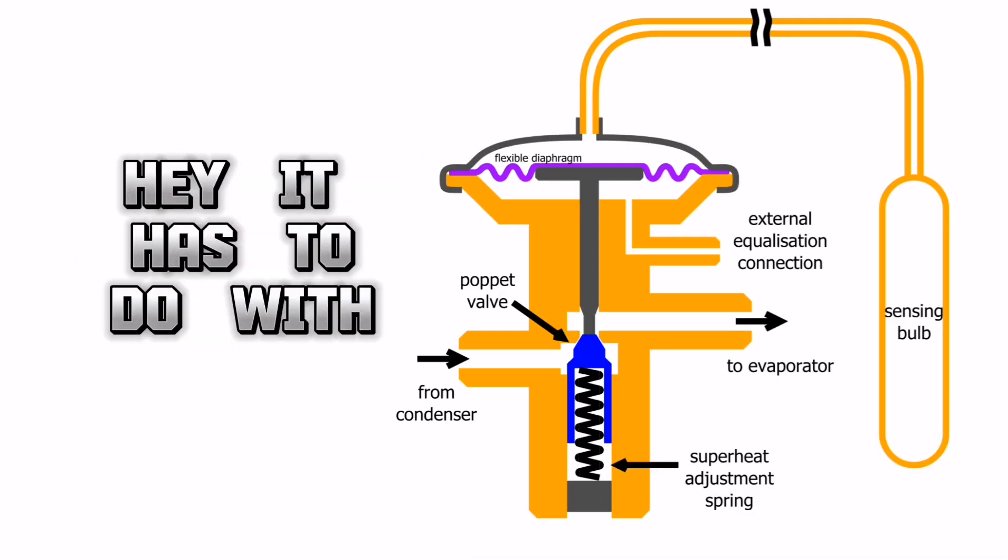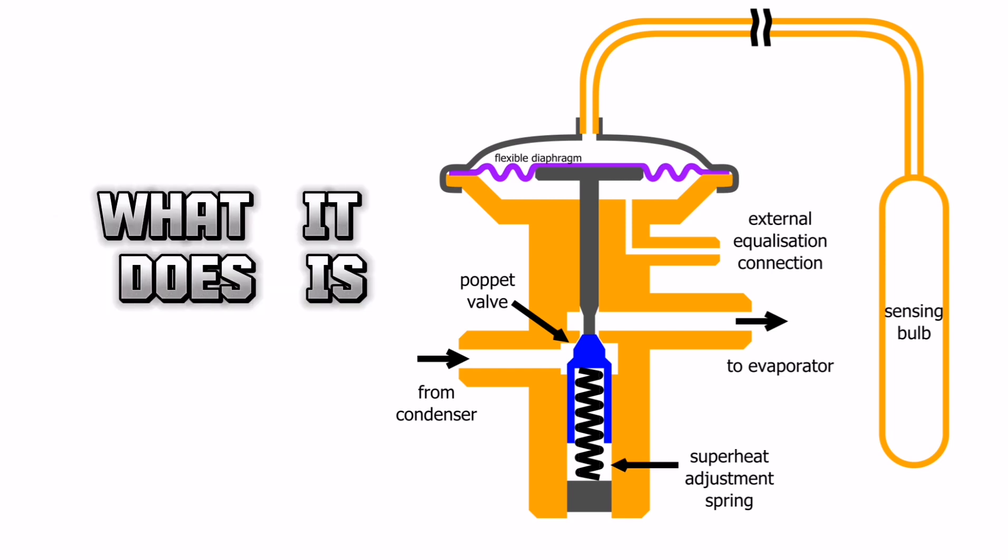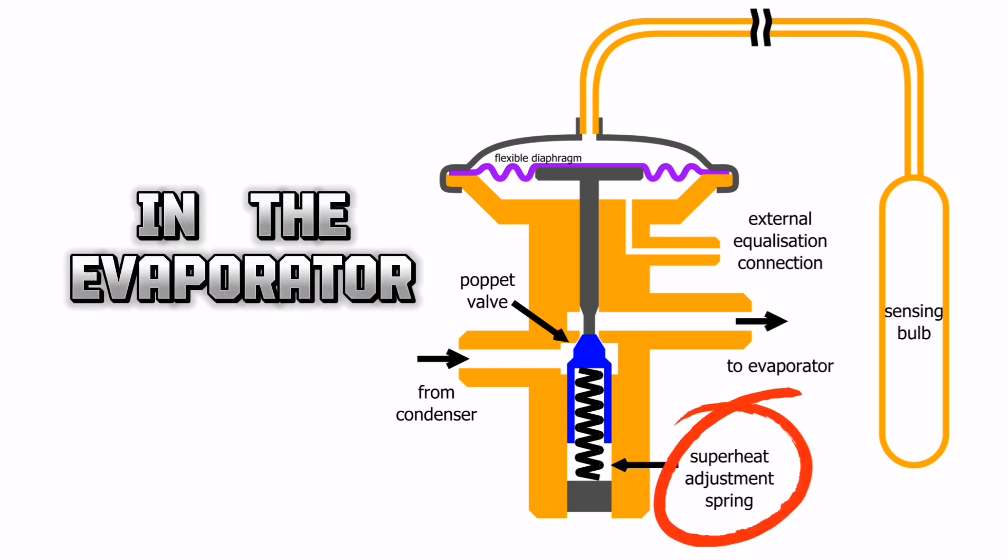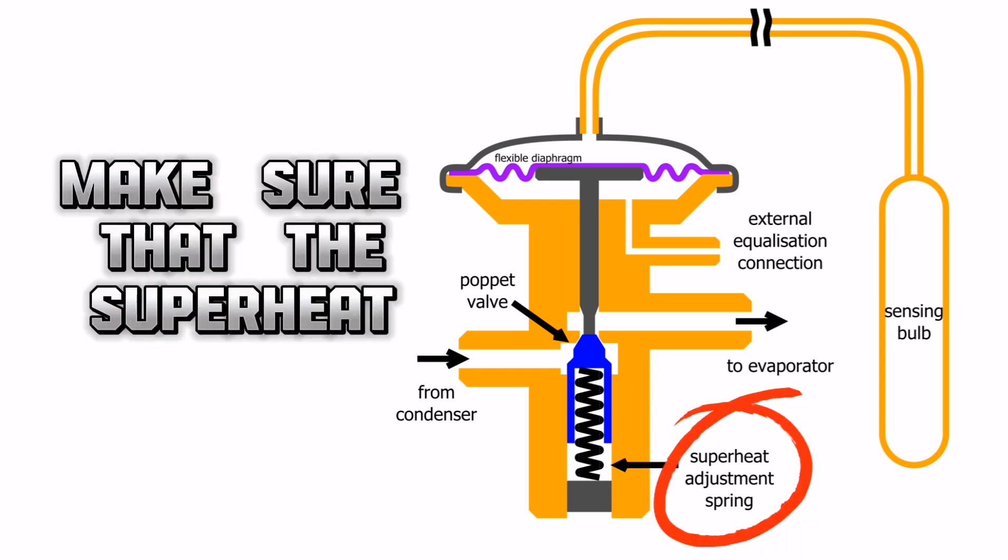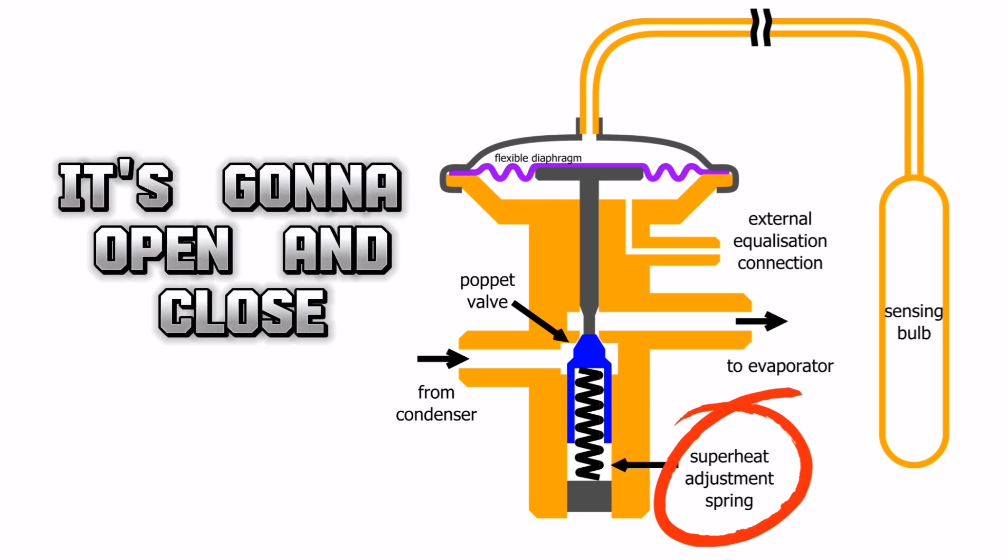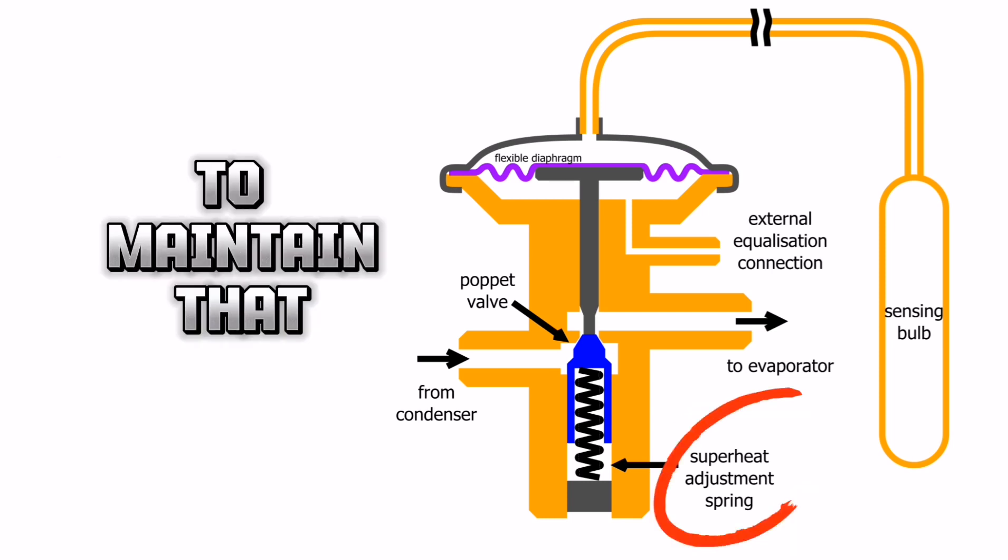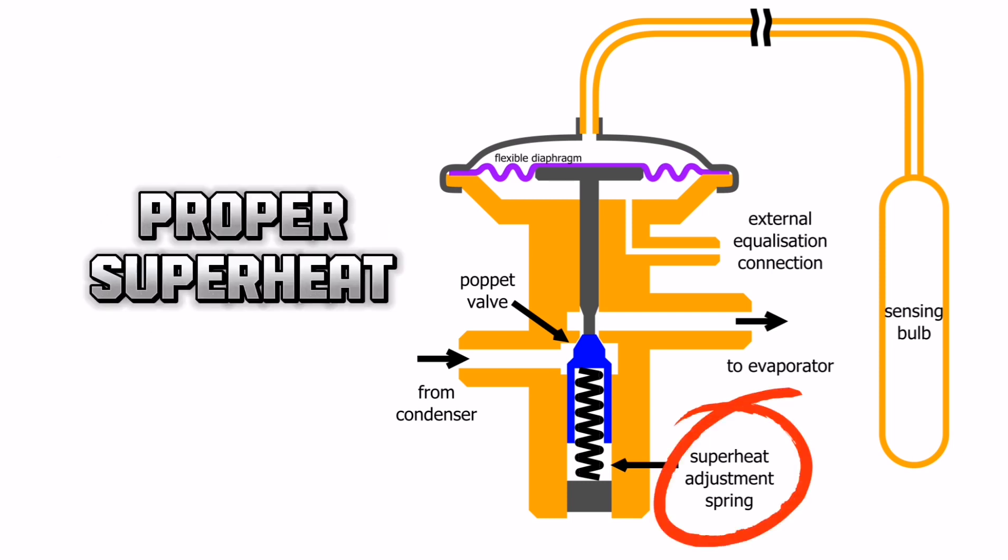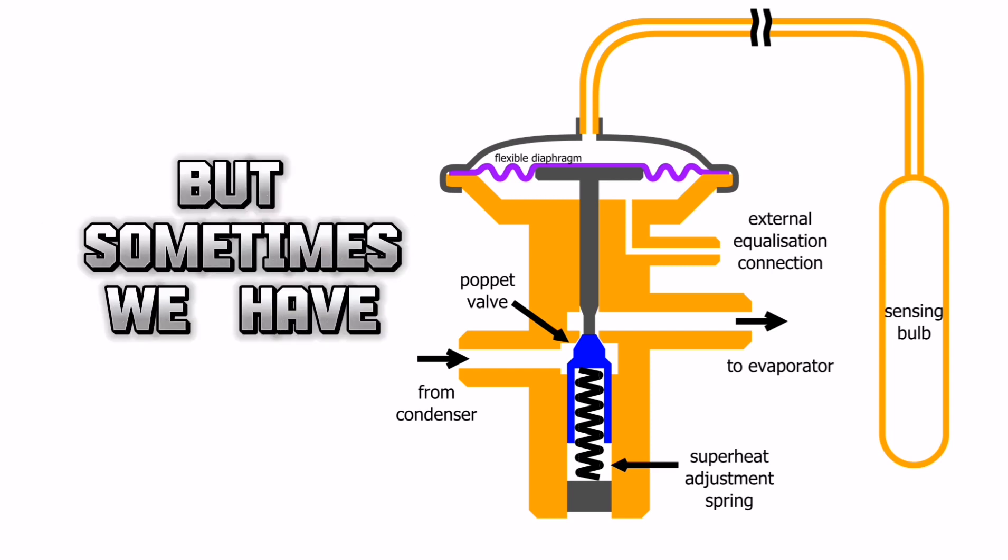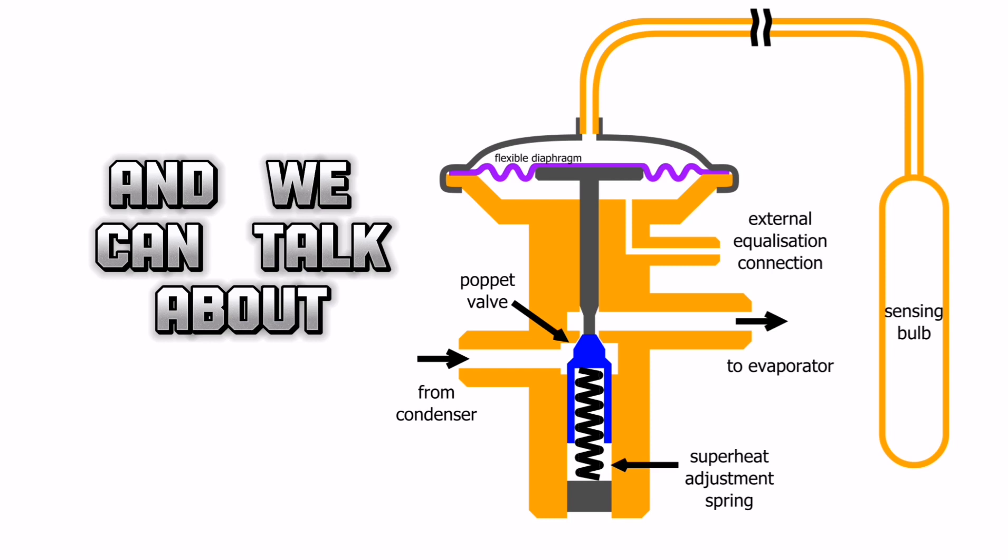We said the thermostatic expansion valve has to do with temperature. But actually what it does is it maintains superheat in the evaporator. Make sure that the superheat in the evaporator is right where it's supposed to be. And it's going to adjust. It's going to open and close to maintain that proper superheat. And usually they come preset from the manufacturer, but sometimes we have to adjust them.